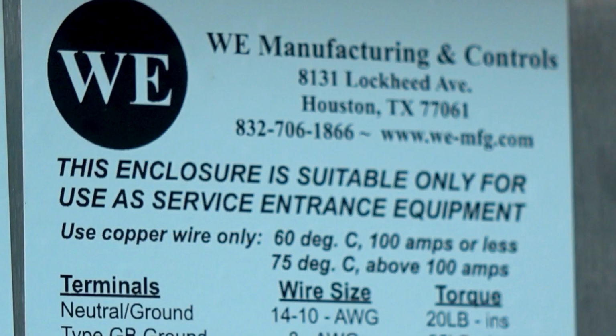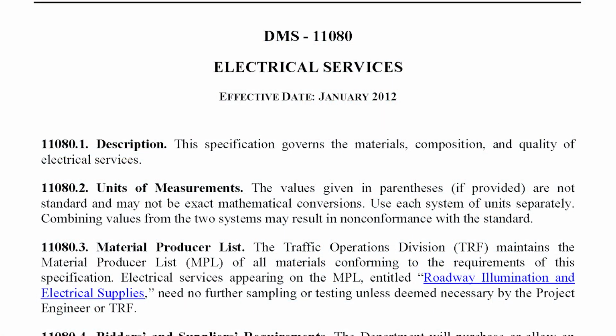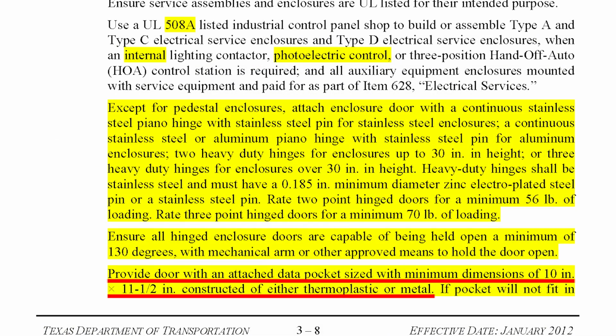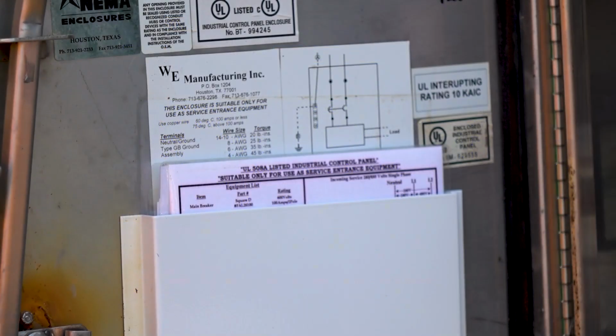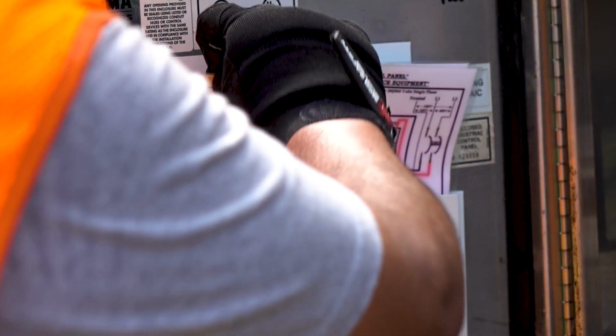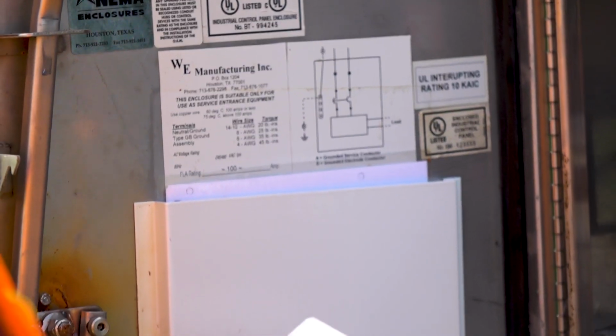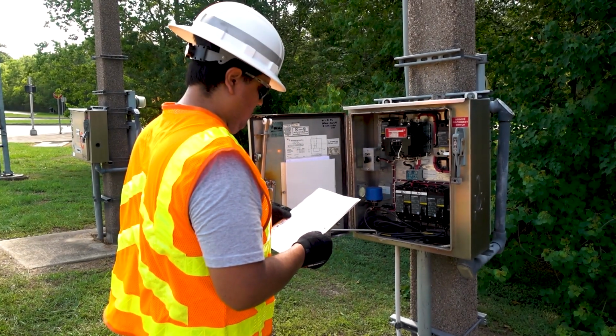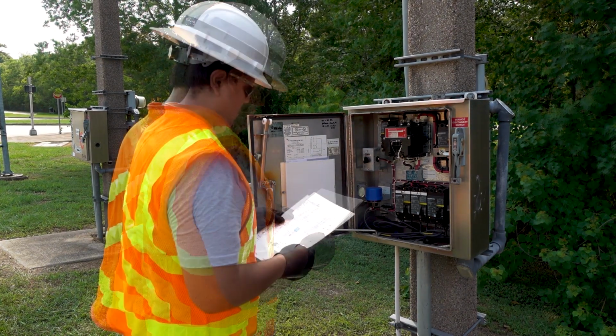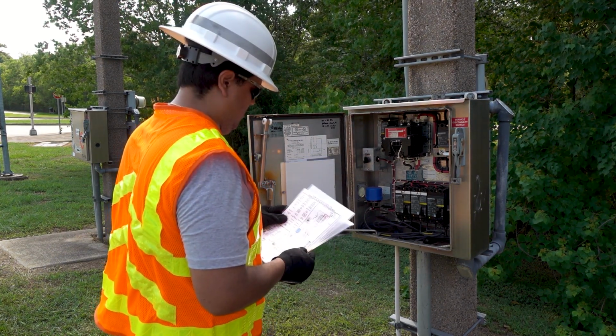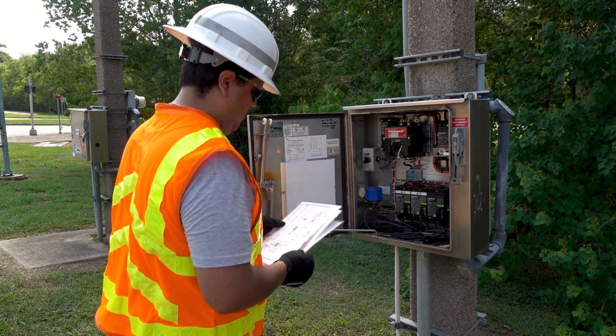The panel must have the words "suitable only for use as service equipment" clearly printed on a label attached to the panel's door. DMS 11080 requires that a document pocket be attached to the inside of this door. It also specifies that a set of laminated drawings be placed in this pocket. The inspector will need to confirm that a laminated sheet showing the wiring diagram from the UL 508 shop has been provided and is in the document pocket.